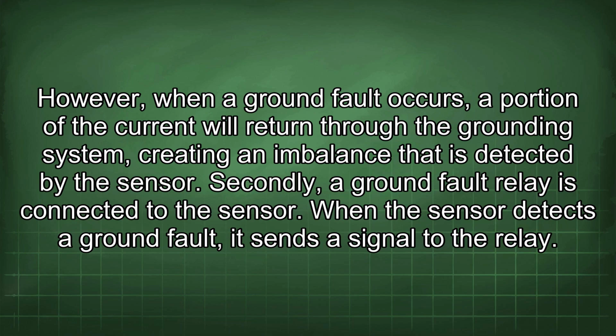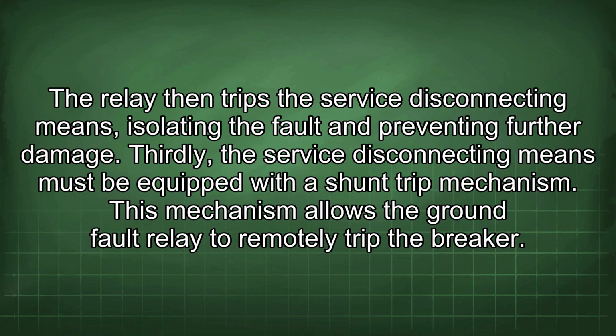Secondly, a ground fault relay is connected to the sensor. When the sensor detects a ground fault, it sends a signal to the relay. The relay then trips the service disconnecting means, isolating the fault and preventing further damage. Thirdly, the service disconnecting means must be equipped with a shunt trip mechanism. This mechanism allows the ground fault relay to remotely trip the breaker.